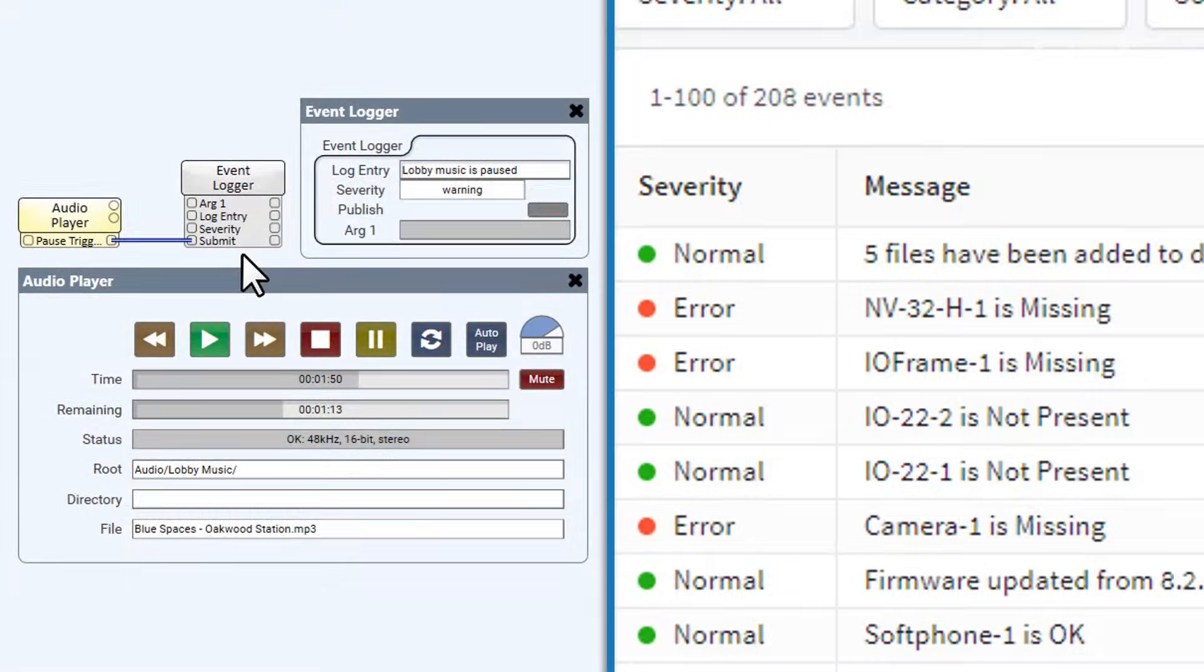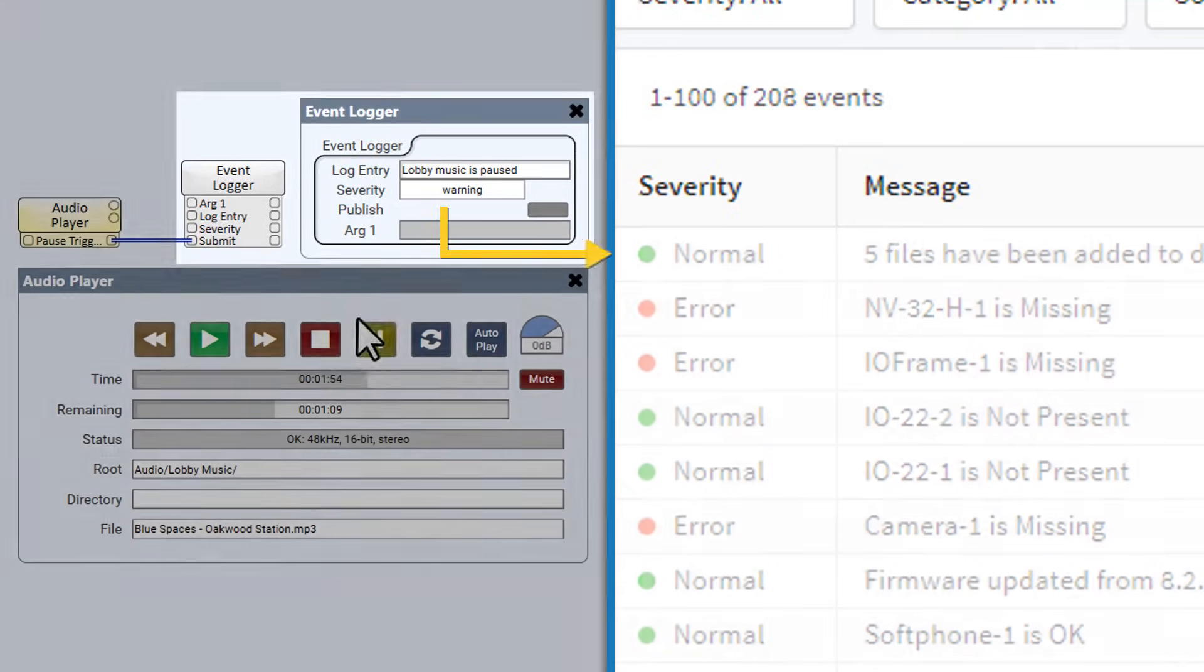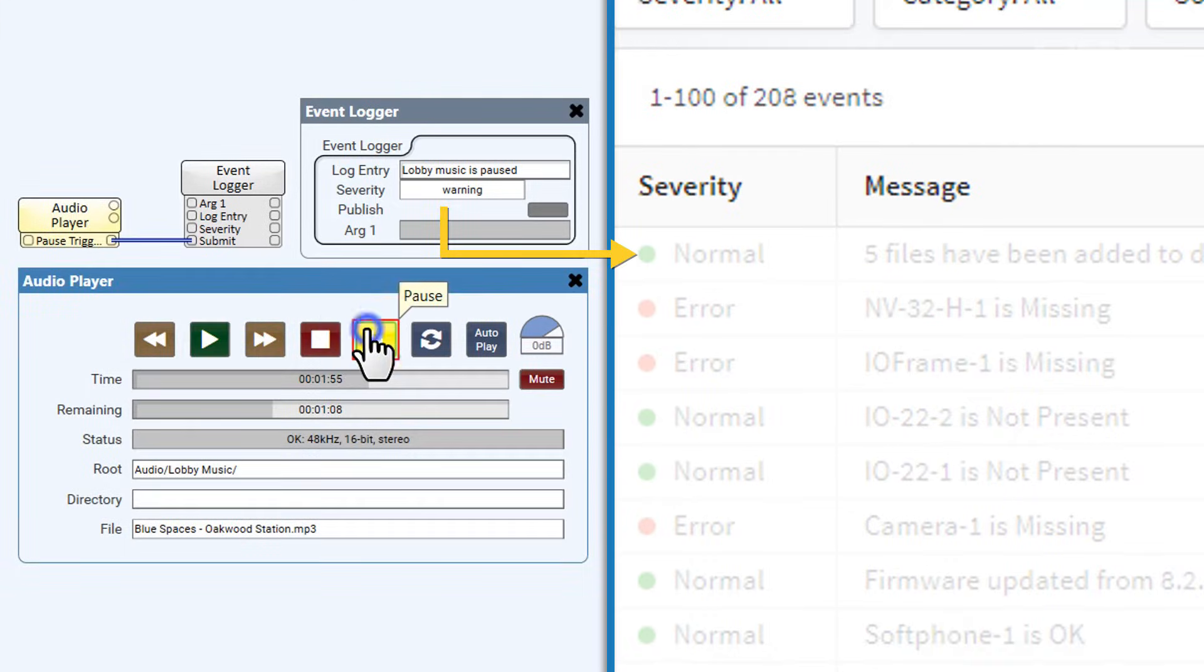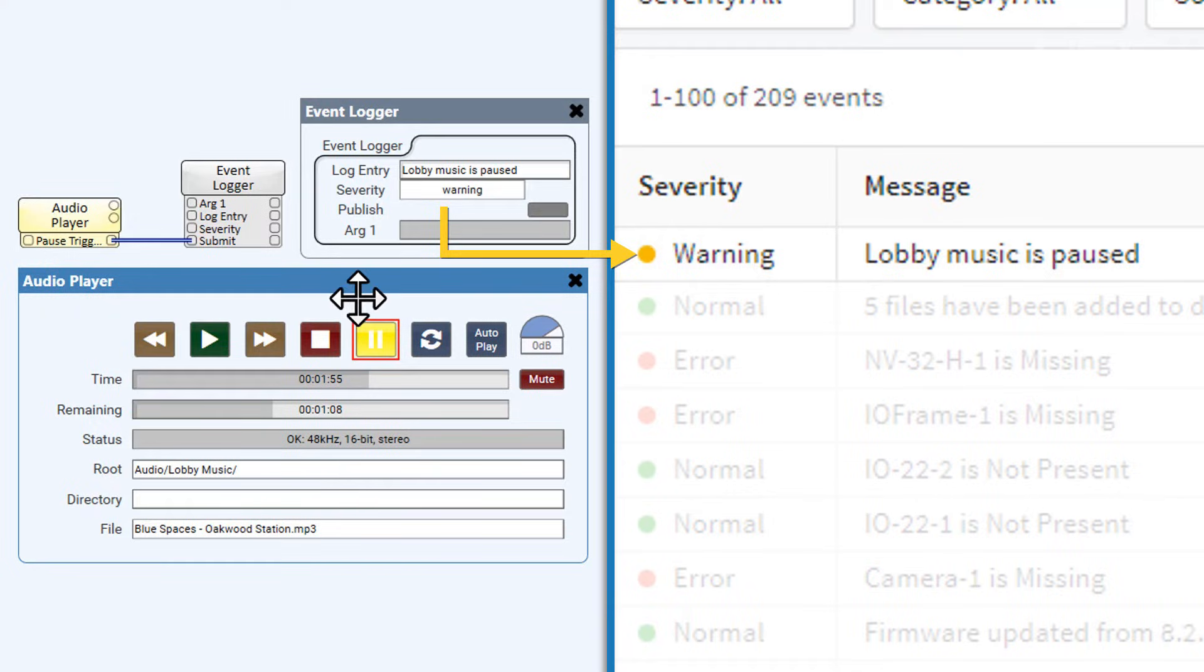There are certain components that allow you to publish custom messages to the Event Log based on your design's activity, which makes this a useful troubleshooting tool to keep track of your entire system's performance. Core Manager will store up to 5,000 events, or 30 days' worth of activity, whichever one comes first.